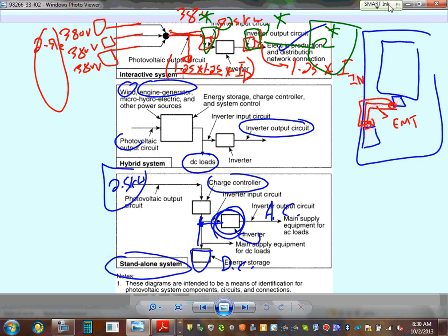On this side, guys, on all these also, they put a label that says both the line side and the load side could be energized. Because a lot of us, you have a disconnect, you disconnect it, this is dead, right? And this is alive. In an AC system, by the way, both sides of the disconnect could be alive, because when you disconnect it, you're just not putting power into the grid. So there's a lot of issues, guys, involved in the disconnect.